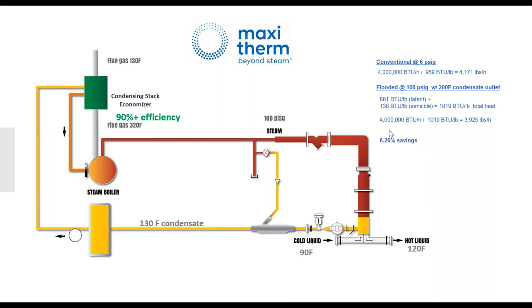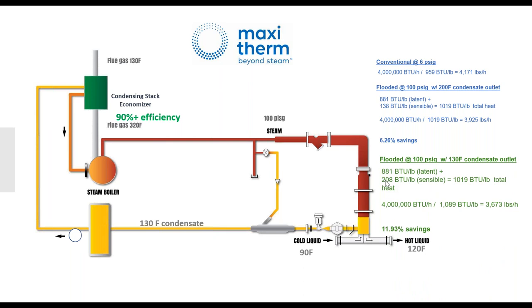If we were using 6 psi also, this number will be more like 3%, okay? But what is the number if we're coming at 100 psi and the condensate is leaving at 130 Fahrenheit? Survey says 12%. So the concept is you're using 12% less steam at the point of use, whether for building heat or even domestic hot water, right?